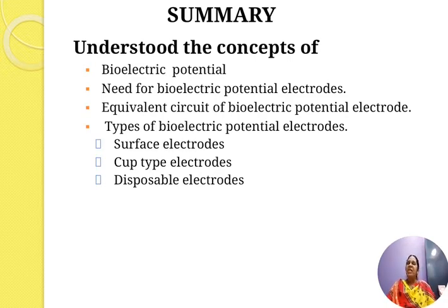They are of many sizes and types. In spite of their type, any surface electrode can be used for measurement of ECG, EEG and EMG. The types of surface electrodes are metal plate electrodes, which are used for applications to limbs, metal disc electrodes which can be applied with surgical tapes, and disposable foam type electrodes. Then we have the body surface electrodes, which I have already discussed, and the suction cup electrodes.